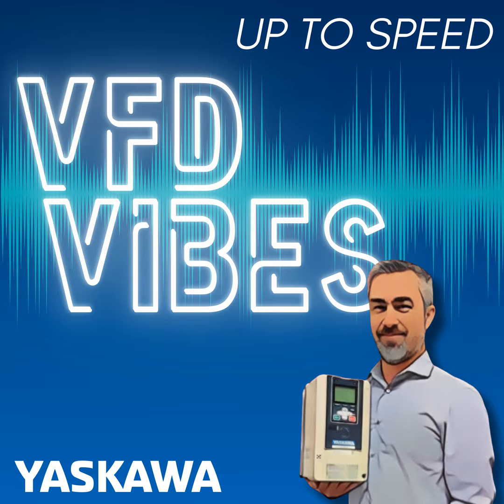If we go back, there's a standard for grounding a system, but let's answer the question, why do we need it? We've talked about the arc flash and the protection of people. Are there any other reasons? What if we tried to run a whole facility on an ungrounded system? Well, there are whole facilities that run on ungrounded systems, and they do this because, again, you can have a fault from line to ground, and it doesn't shut the building down.